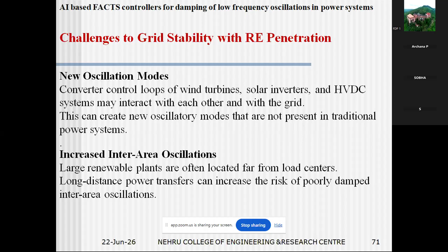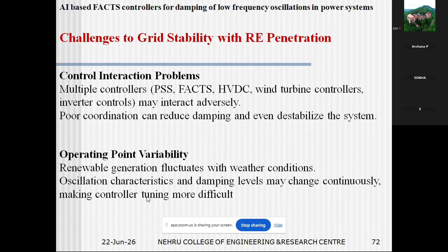Similarly, conventional systems will have PSS. Then HVDC definitely has become a part of the system. FACTS devices are required, so there will be wind turbine controllers and inverter controllers. All of these will interact with each other. Poor coordination is again another reason which can destabilize the system. Then operating point variability. Renewable generation, as I told you, is totally stochastic in nature. You cannot predict it. It will fluctuate with weather conditions, so controller tuning becomes more and more difficult.